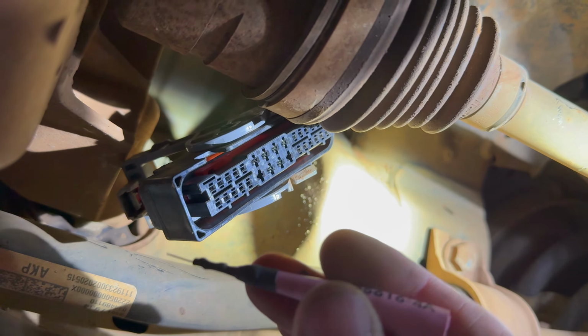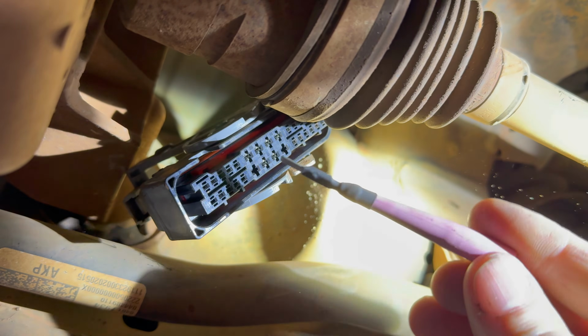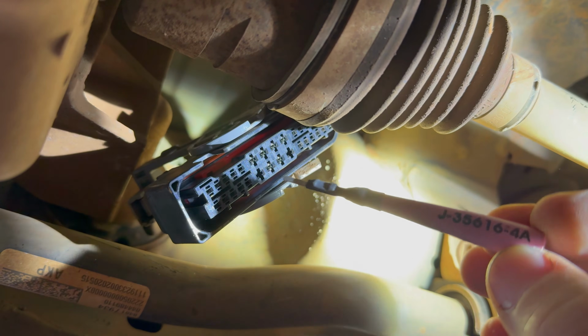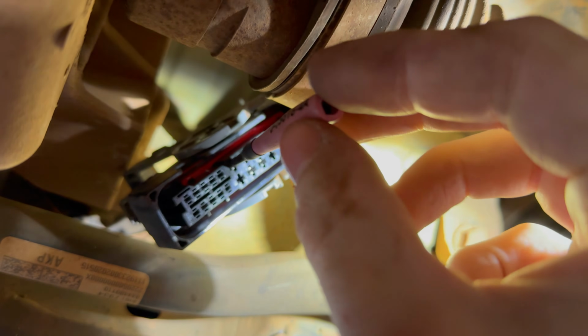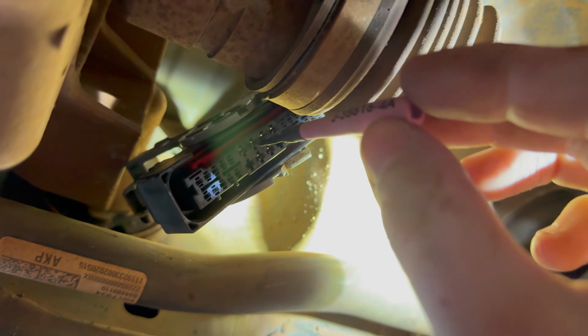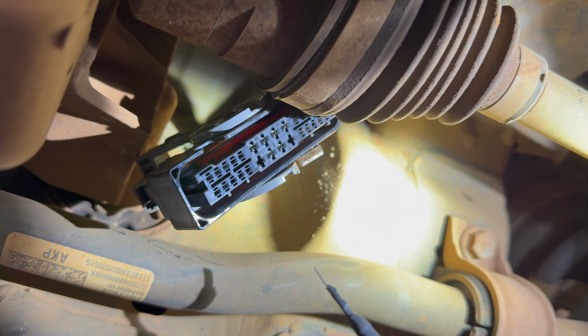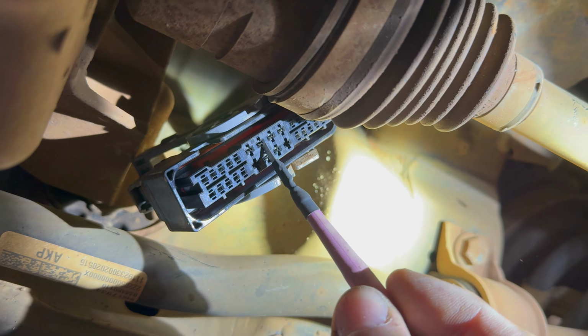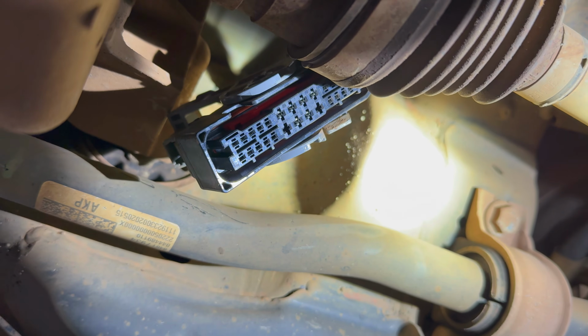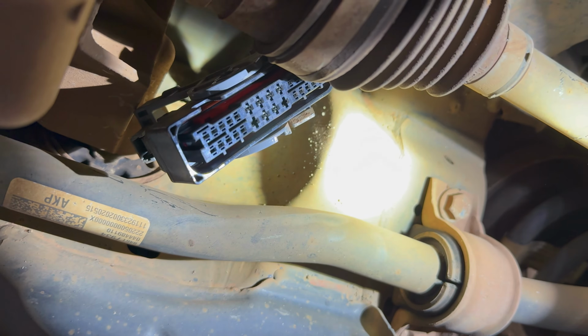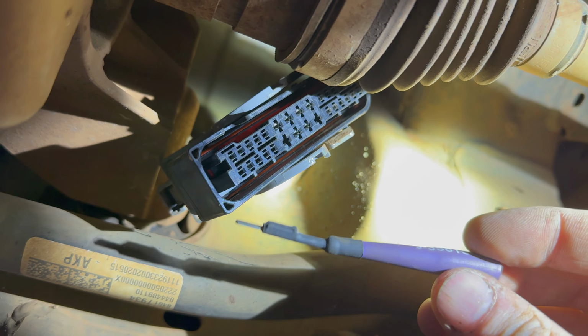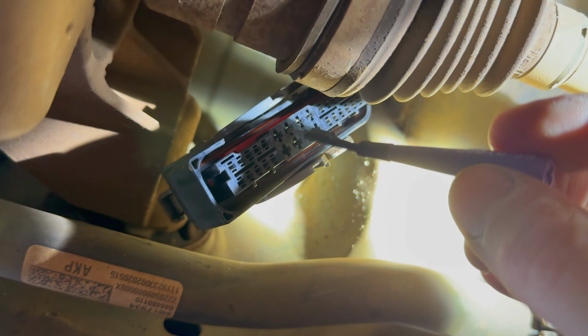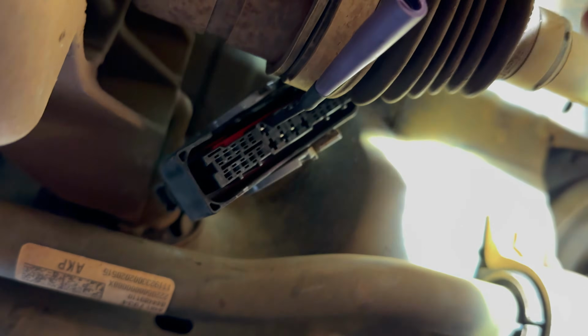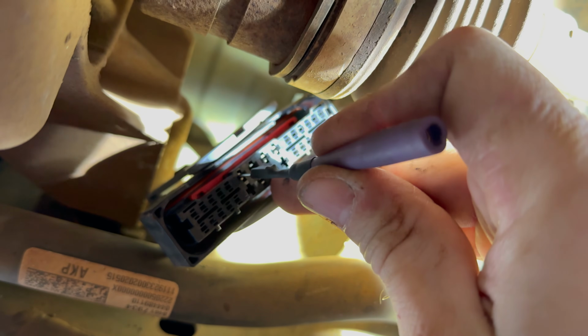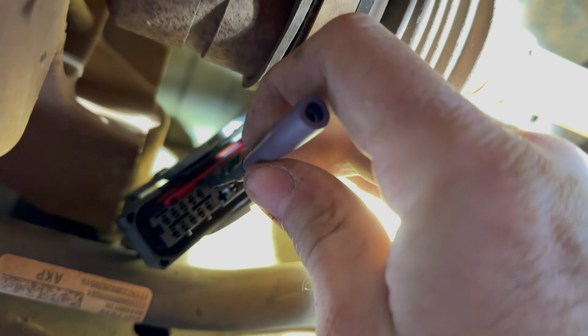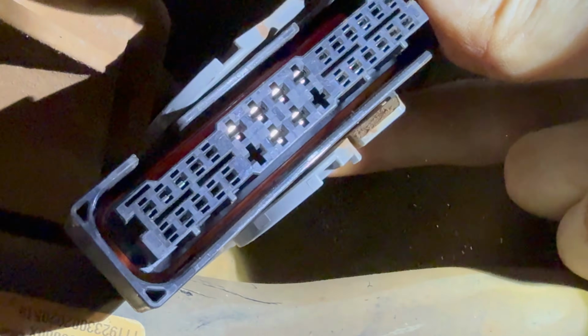Alright, so I was doing a little research on this loose terminal thing, and the service information says to use this probe on terminal 21, and it fits loosely into that one, fits loosely into all of these really. The adjacent terminal 22 right here actually calls for a different one, this one I just dropped. Terminal 22 calls for this test probe, and that one fits nice and tight in both of these.